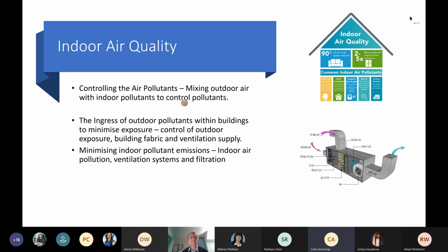Building air tightness. Once a contaminant from outdoor sources reaches the building, the extent of pollution ingress will depend on the air tightness of the building envelope and the number of openings, as well as the ventilation strategy. Gaps and cracks in the building envelope contribute to the air permeability of the building. Therefore, reducing air permeability by sealing the building envelope and increasing its air tightness will help reduce air ingress and so the air pollution.